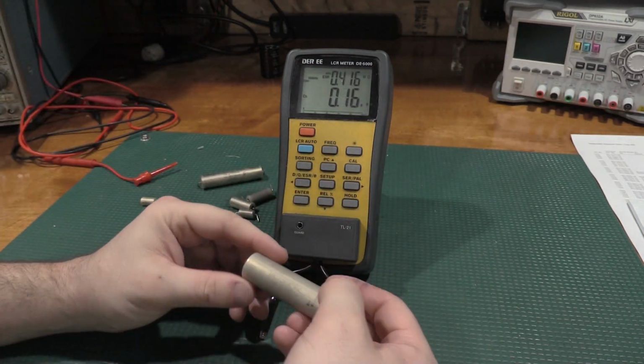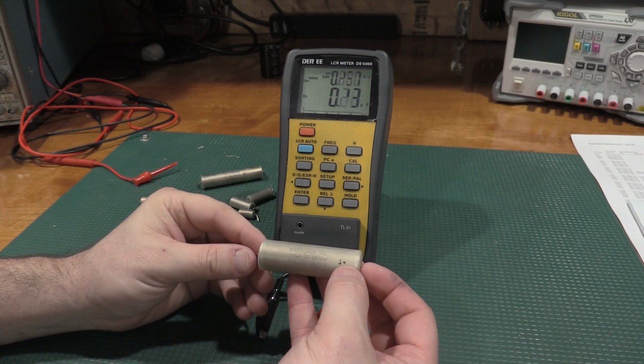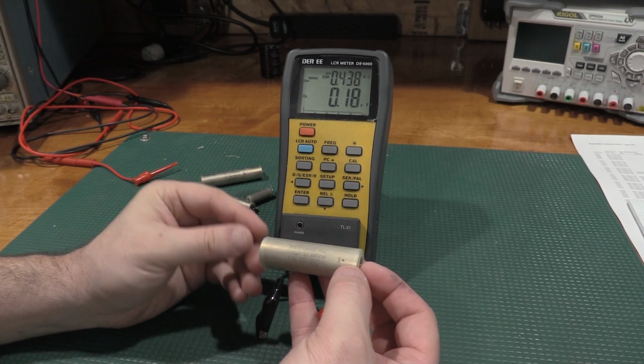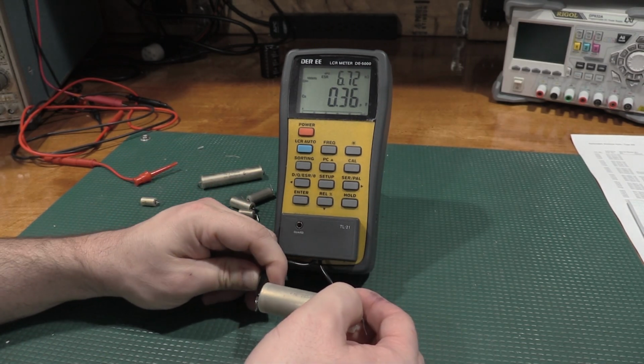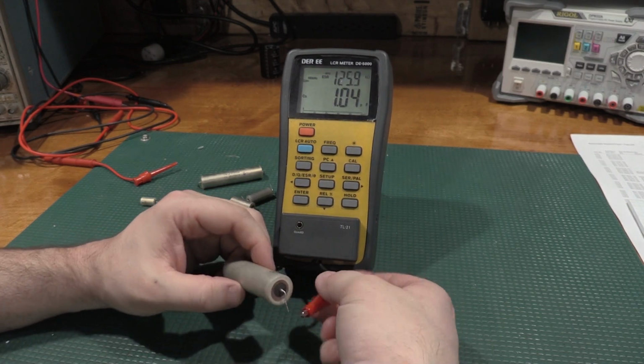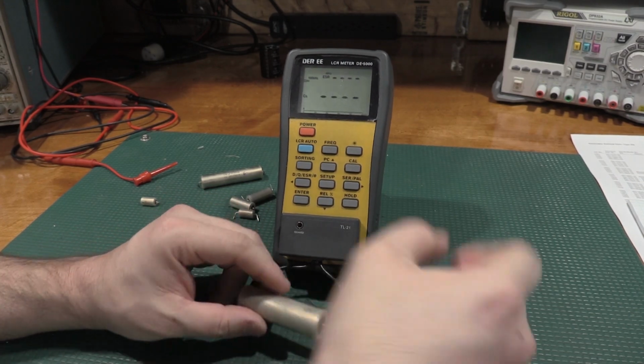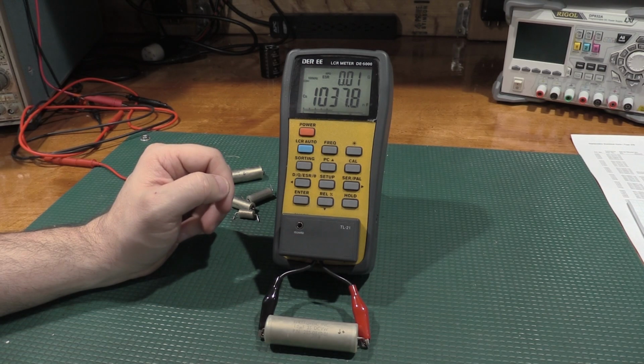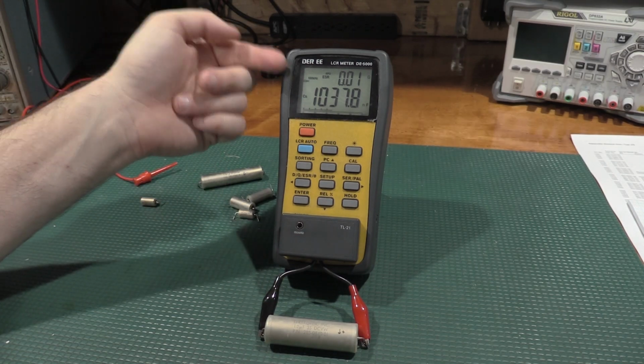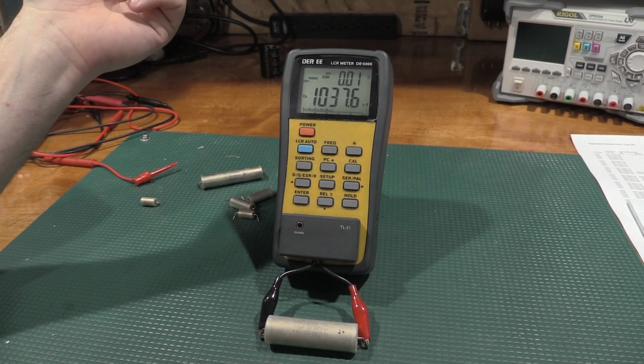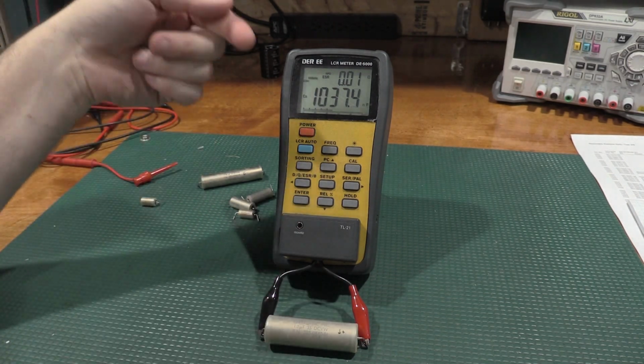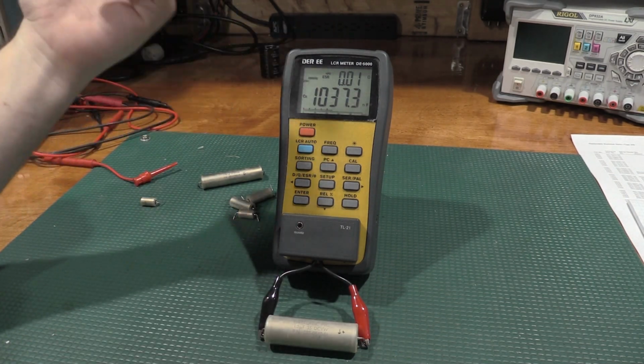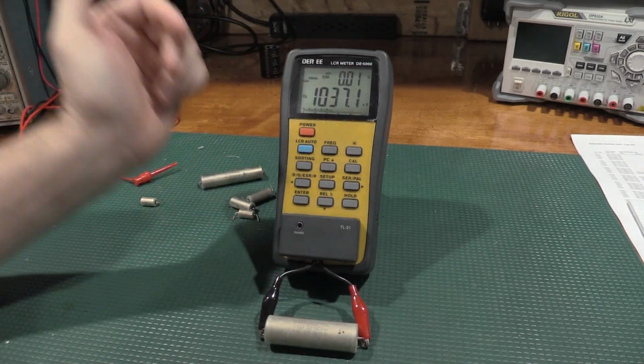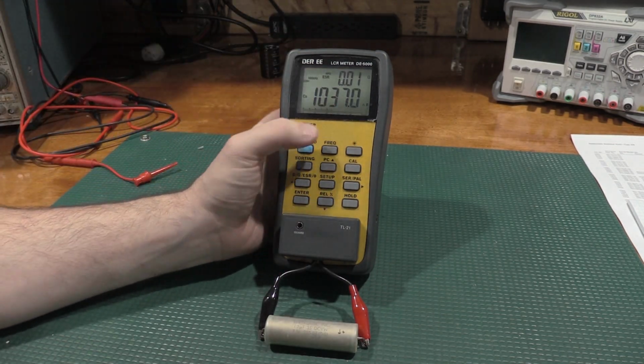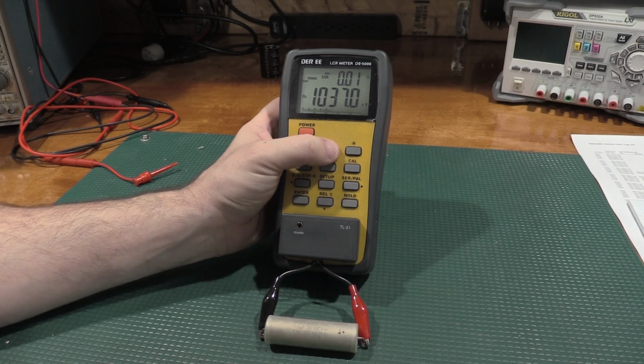We'll go to the other side of the spectrum with a 1 microfarad, 35 volt capacitor, and we'll hook this up this way. Testing this at 100 kilohertz, we have 0.01 ohm of ESR, and we're pretty good. 1.03 microfarads, so we're pretty good there. But let's check what happens when we drop the frequency down.